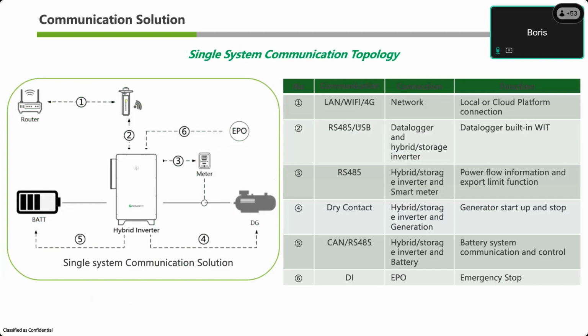The inverter does support dry contact generator startup, and we have a mode to program that in, so you can set battery SOC start and stop in order to turn on an external generator, and I'll show you later on how that might look in a system. And then the last thing to note is that our batteries do communicate over CAN, but that happens all through the inverter, so that's not expected at the end user. They don't have to use any of that. We can just do it all through Modbus.